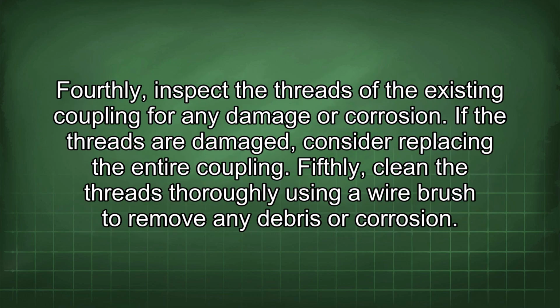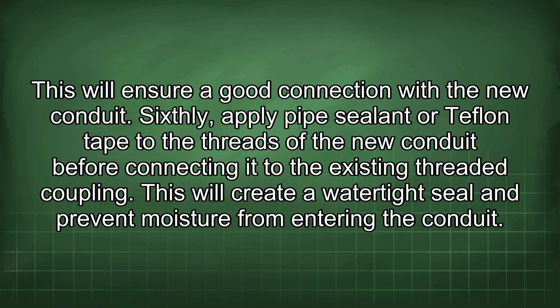Fourthly, inspect the threads of the existing coupling for any damage or corrosion. If the threads are damaged, consider replacing the entire coupling. Fifthly, clean the threads thoroughly using a wire brush to remove any debris or corrosion. This will ensure a good connection with the new conduit. Sixthly, apply pipe sealant or Teflon tape to the threads of the new conduit before connecting it to the existing threaded coupling. This will create a watertight seal and prevent moisture from entering the conduit.